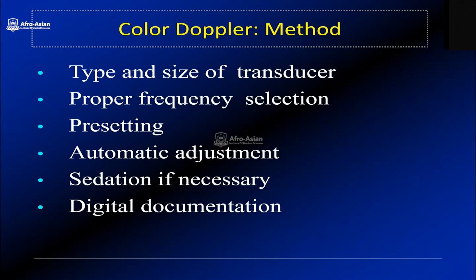For instance, if we have a convex transducer having 3.5 and 5 megahertz, we will prefer to use the higher frequency, which is 5 megahertz, in that specific convex transducer.